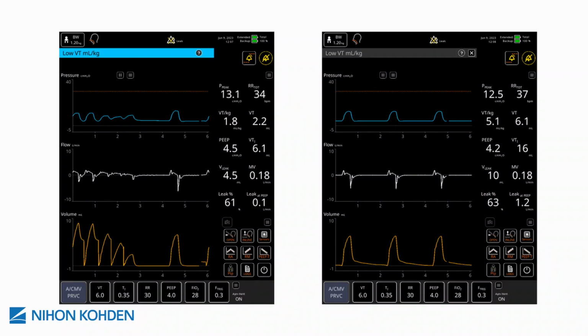This ventilator can actually quantify the leak, which is really helpful. As I just walked through this, the tidal volume set is 6 mLs. This ventilator measures tidal volume at different points and can actually calculate what's actually delivered to the patient. So what leaves the ventilator is 6.1 mLs. What's delivered to the patient is 2.2 mLs. And so the leak percent is around 60%. As it then adjusts in the second picture here, the leak is still around 60%. What leaves the ventilator, though, again with this additional flow, is 16 mLs, and what's delivered to the patient is back to 6, which is exactly what we have set up. So the technology of the ventilator is responding such that the patient is overcoming some of the technical issues and is still getting what they need. You can imagine if the tidal volume is cut by 2/3, the patient is going to have hypercarbia and desaturation.